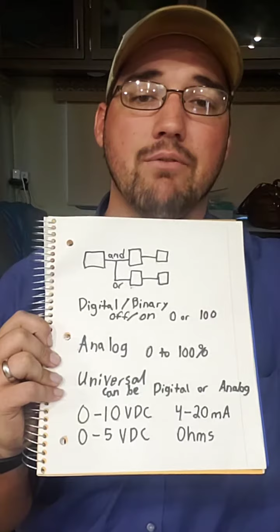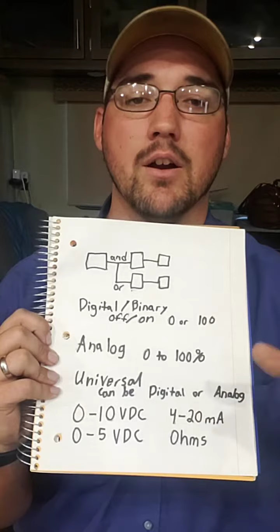Like I said, if it is a milliamp system and you want to know how many milliamps I am giving that controller, or that component, you'll have to unwire the signal wire, wire your meter leads into it, and run the signal through your meter so that you can actually see what that signal is. So just keep that in mind. A 0 to 10 volt DC could be a binary or an analog signal. It could be 0 to 10, or it could be 0 or 10 volts, depending on the setup. Same thing with 0 to 5.